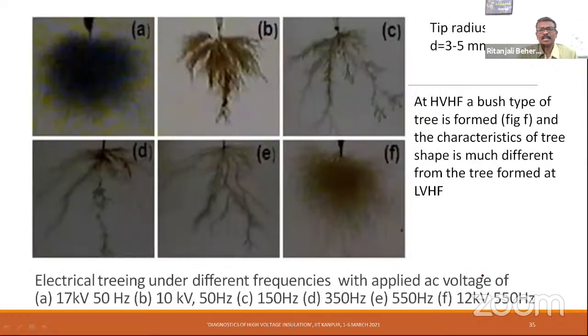In this picture, the first one, A, is at 17 kV 50 Hz - that's completely a bushy tree. The second, B, is at 10 kV 50 Hz, where the only difference is the voltage. When the voltage is reduced, with the frequency the same, it gives more of a branchy, bush-branch type structure.